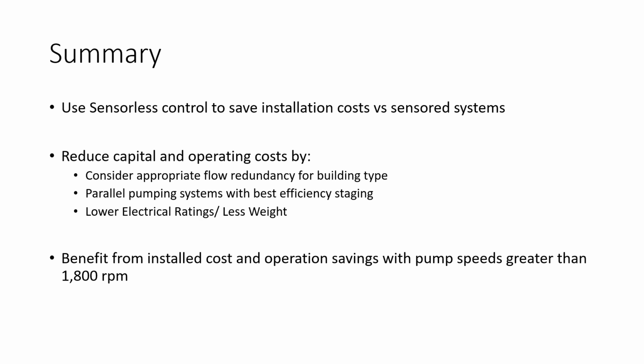So why do we use it? We use sensorless control to save installation costs versus sensored systems. No more putting a sensor in the wrong spot or having an enormous run of wire just to have a slow reacting system. It'll reduce the capital and operating costs by having the appropriate flow redundancy for the building. Parallel pumping systems will run in a best efficiency staging, and you'll have lower electrical ratings with a lot less weight. And the benefit from the cost and operation savings of pump speeds greater than 1800 RPMs as well.